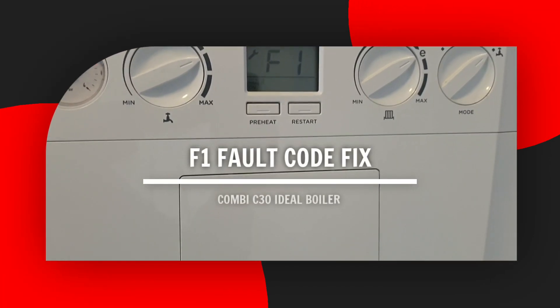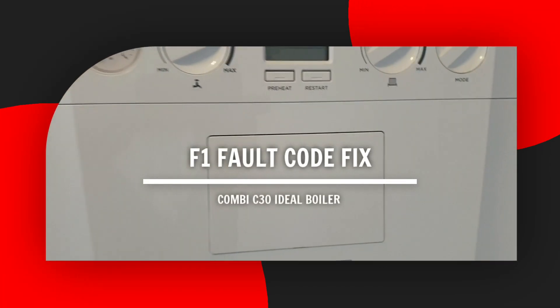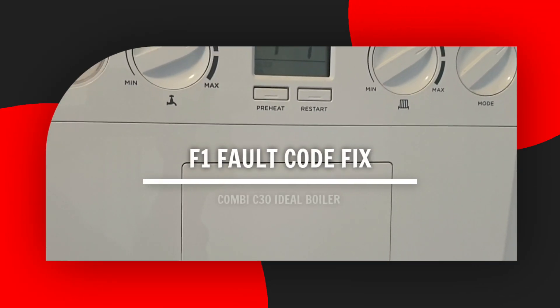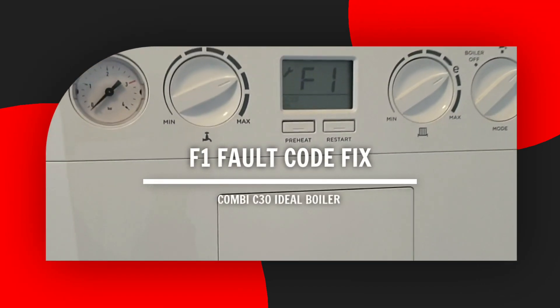Today we'll be looking at the F1 fault code on the C30 Ideal boiler. The F1 fault code is mainly a result of low boiler water pressure in the boiler.